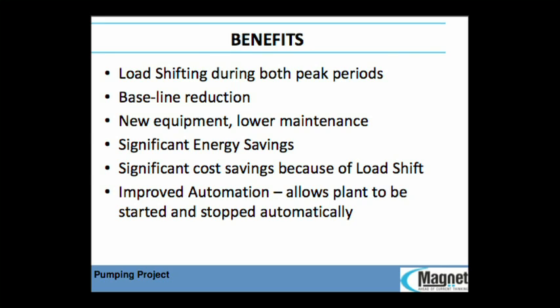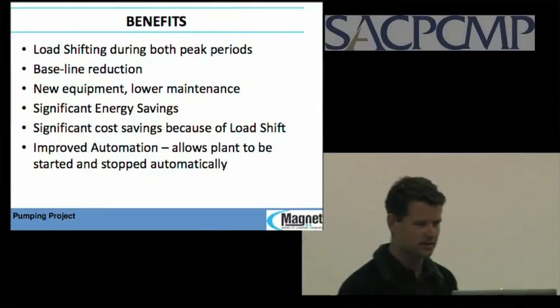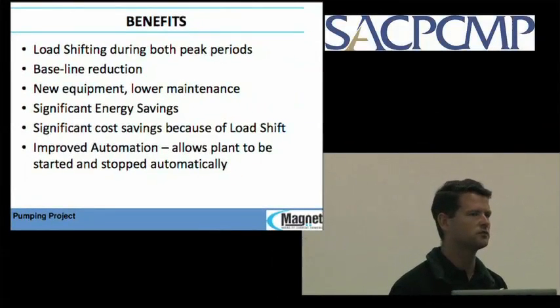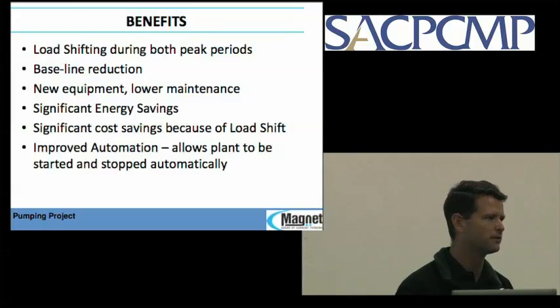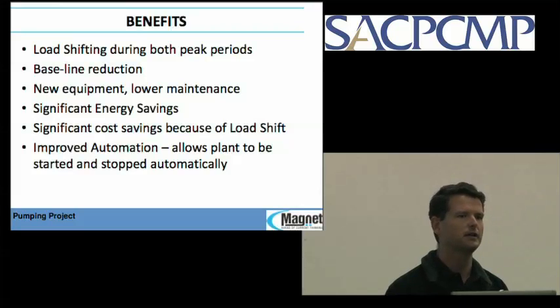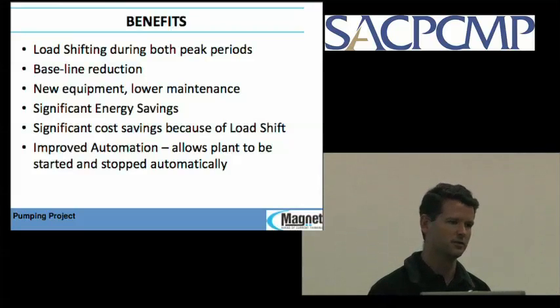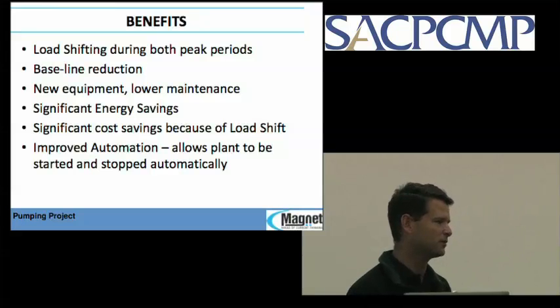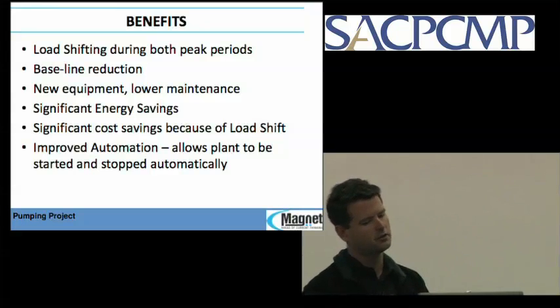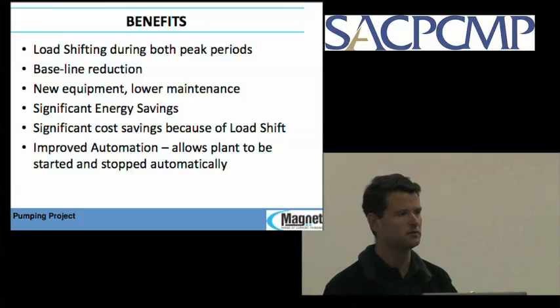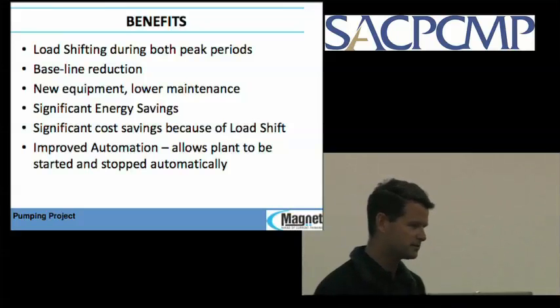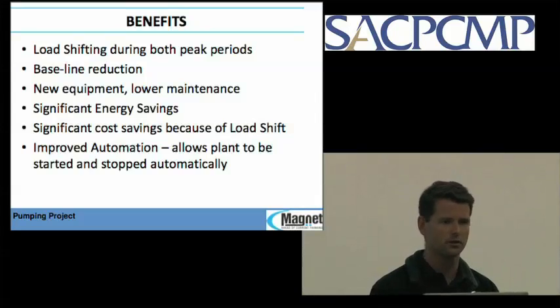So what are the benefits? Load shifting during both peak periods. Load shifting is extremely cost effective for a plant, and I'm looking at some refrigeration projects now where they've got ice dams and things like that. Because your peak energy cost between 6 and 8, I think in winter, depending on your tariff, is about R1.50 to R1.80, and it's more than double what you're paying during normal periods. And even in summer, it's about double, but it's just a lower rate. So if you can move load from peak periods to off-peak periods, you can halve your costs. That's not even talking about the efficiency side of it, it's just when you're doing the work.